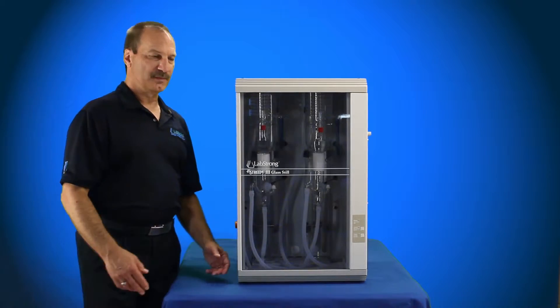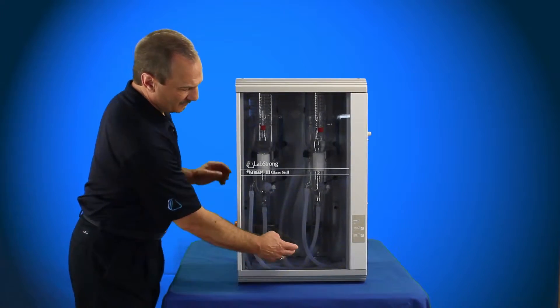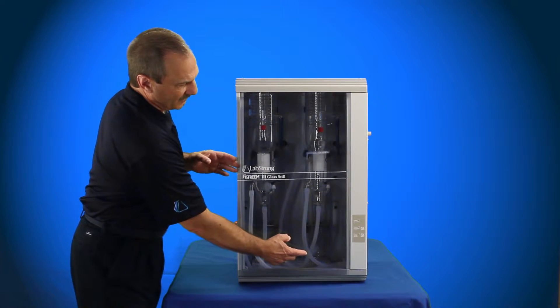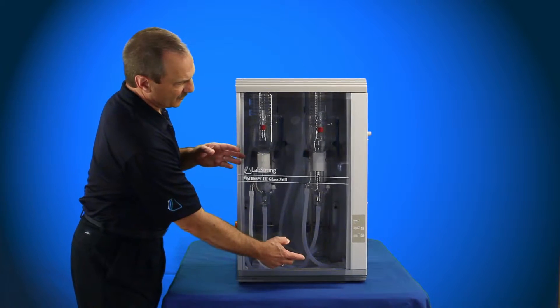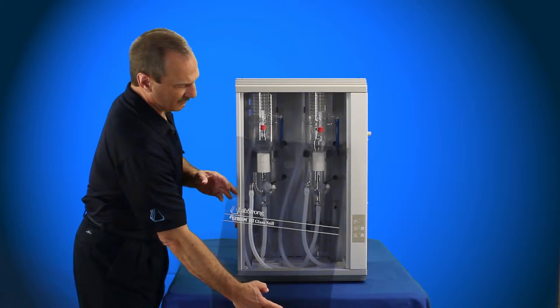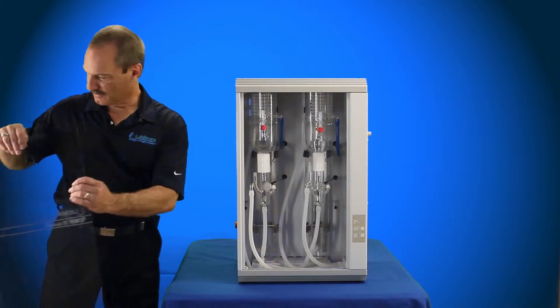Now we're going to remove the door from the 8-liter per hour FiStreem III system. The FiStreem III 4-liter per hour single distilled has the same type of door, it's just a little smaller. You're basically going to lift up, pull out of the bottom, pull the top down, and you remove the door. Set that aside.